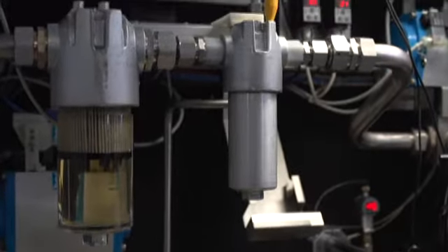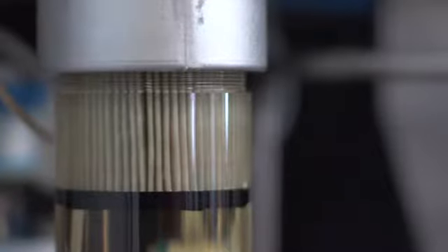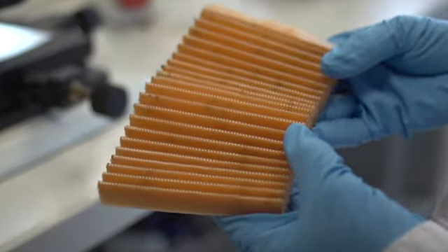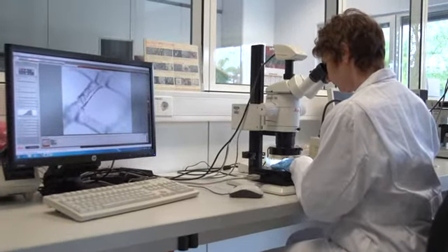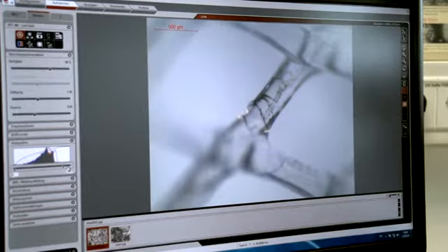These modern oils have low electric conductivity, however, so they are prone to electrostatic charge and discharge, as you can see here in a hydraulic filter element. This type of discharge can cause the system to malfunction. In filter elements, for example, the filter mat is punctured in many places. The level of purity required for the oil can no longer be attained.